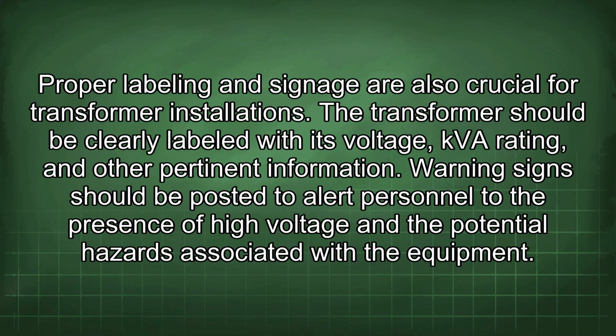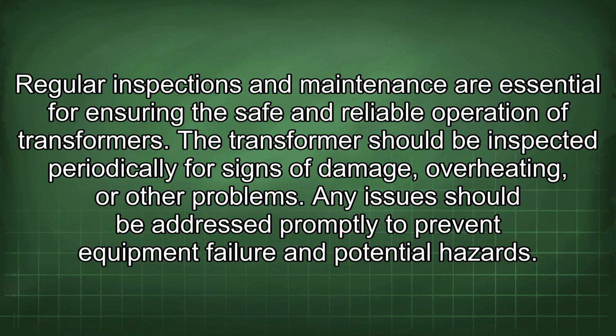Proper labeling and signage are also crucial for transformer installations. The transformer should be clearly labeled with its voltage, kVA rating, and other pertinent information. Warning signs should be posted to alert personnel to the presence of high voltage and the potential hazards associated with the equipment. Regular inspections and maintenance are essential for ensuring the safe and reliable operation of transformers. The transformer should be inspected periodically for signs of damage, overheating, or other problems. Any issues should be addressed promptly to prevent equipment failure and potential hazards.